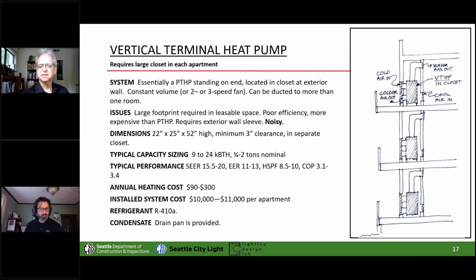Another thing to say, similar to PTAC, it's got that sleeve through the wall. We had an East Coast project where the whole building turned into a giant humidity pump, because this thing sucks this closet negative relative to outside and the apartment. So it's actually even worse than a PTAC because it's sucking air in through the sleeve. We had a contractor do that poorly, and it literally condensed and rained in this building over and over. It's a terrifying thing. So consider ducting the return so you don't have a giant humidity pump.